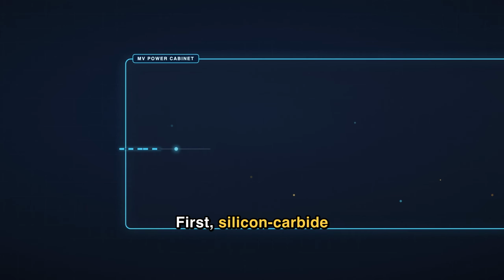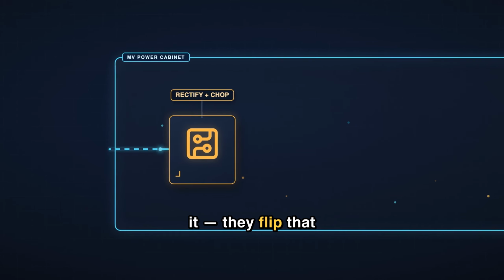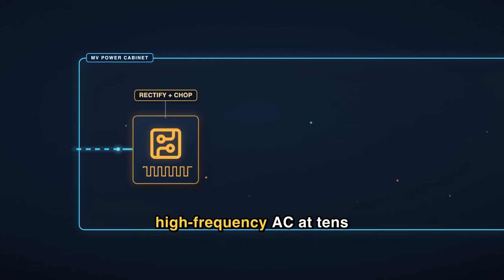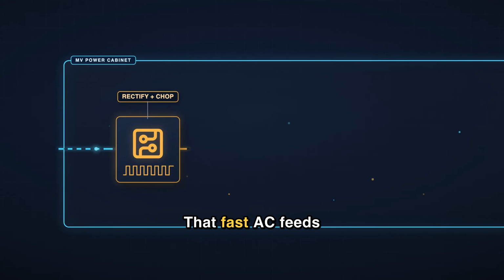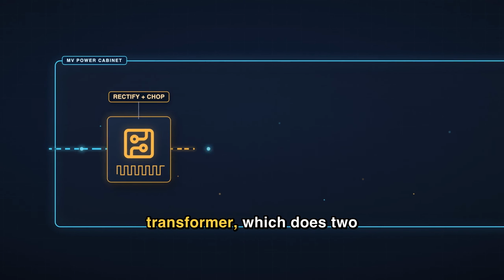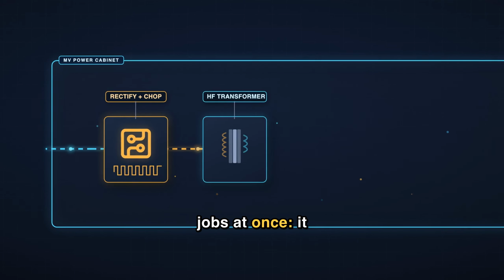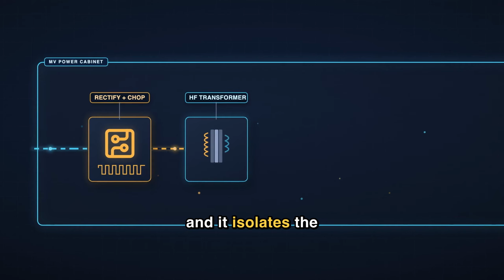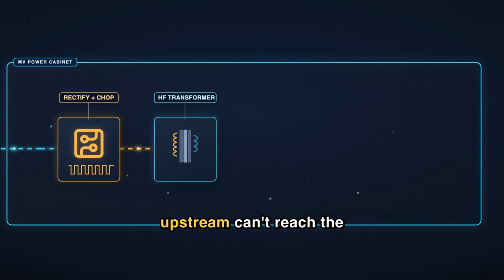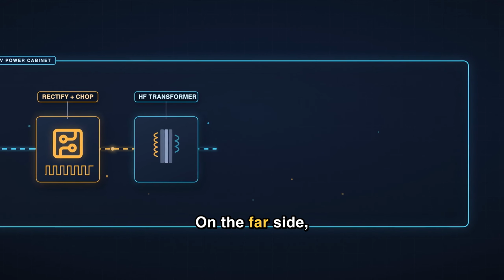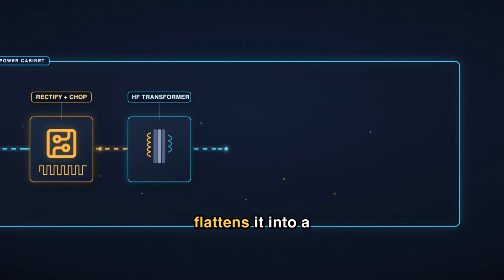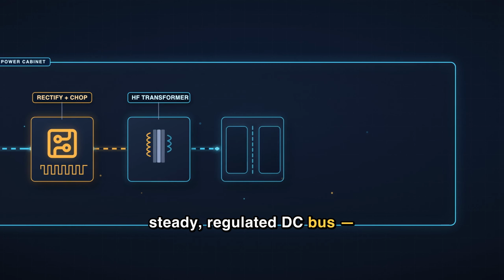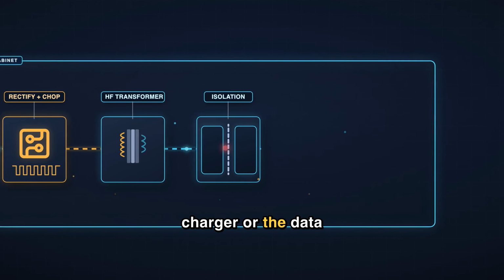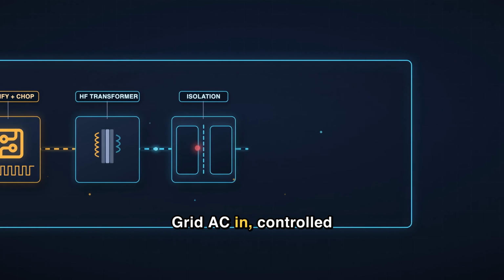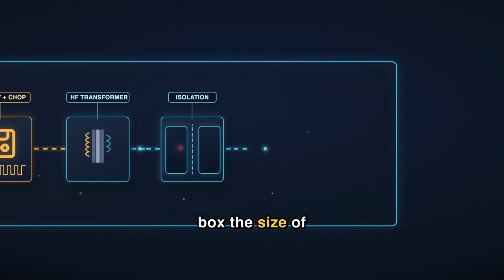First, silicon carbide stages rectify and chop it, flipping that incoming power into fast, high-frequency AC at tens of kilohertz. That fast AC feeds the compact high-frequency transformer, which does two jobs at once: it steps the voltage down and isolates the car from the raw grid, so a fault upstream cannot reach the vehicle. On the far side, one more rectifier stage flattens it into a steady, regulated DC bus, the clean voltage the charger or the data hall plugs into. Grid AC in, controlled DC out, through a box the size of a cabinet.